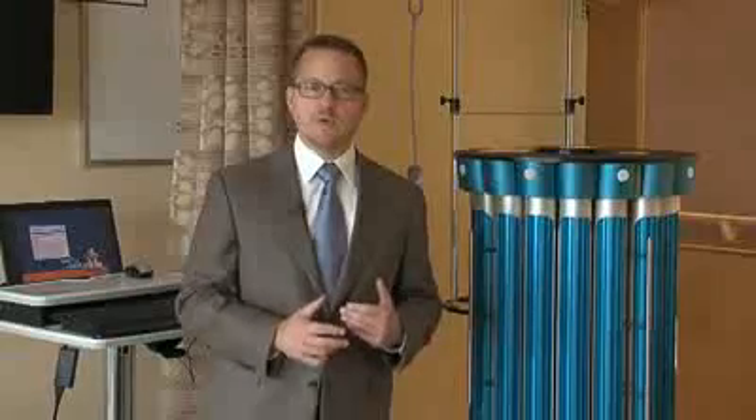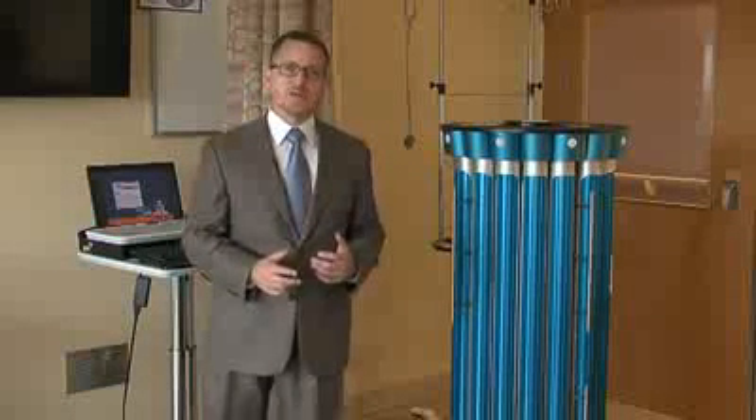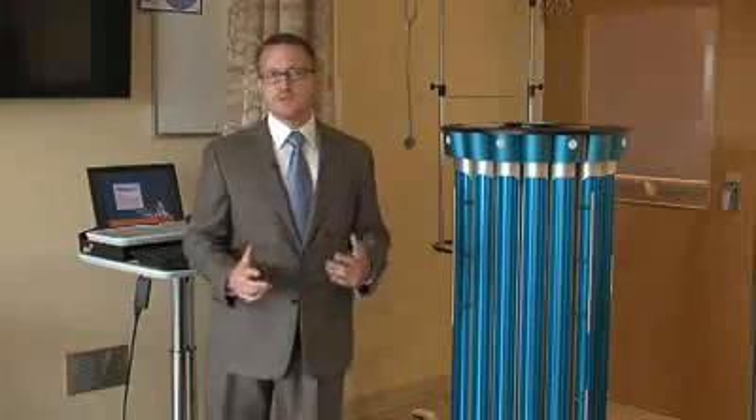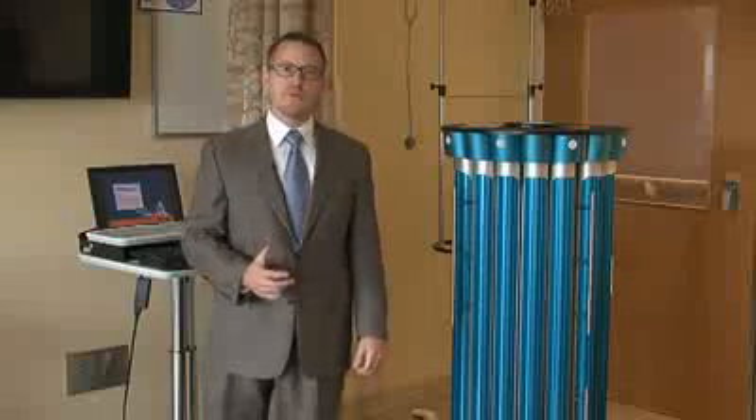I'm going to go over the features and functions of the IRS 3200M and a little about the technology behind what we do. The IRS 3200M is an ultra-high-intensity UVC-generating device. UVC is a disinfecting wavelength that pierces the cell membrane of a microorganism and cross-links the DNA and RNA so that the organism is no longer able to make proteins and function. UVC has been used for many years for water treatment, air disinfection, and in microbiology laboratories' high-level biosafety cabinets. The IRS 3200M is an adaptation of that UVC technology, enabling a healthcare facility to use UVC in a regular, standardized way to treat an entire room — something that hasn't been possible previously.